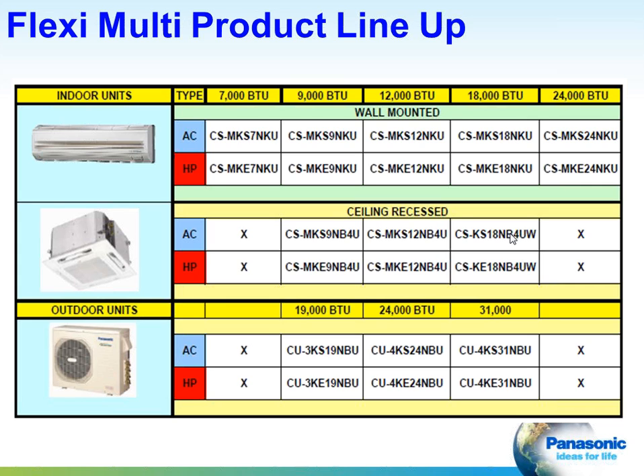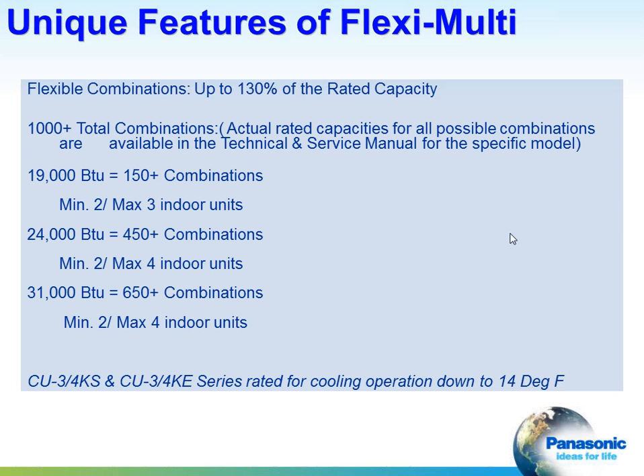You can use a variety of indoor units up to 130% of the outdoor unit capacity, so that means you can mix the style of the indoor unit and have different capacities as long as you don't exceed, in terms of BTUs, 130% of that outdoor unit capacity. Many different combinations are possible. There's over 1,000 with these 3 different systems.